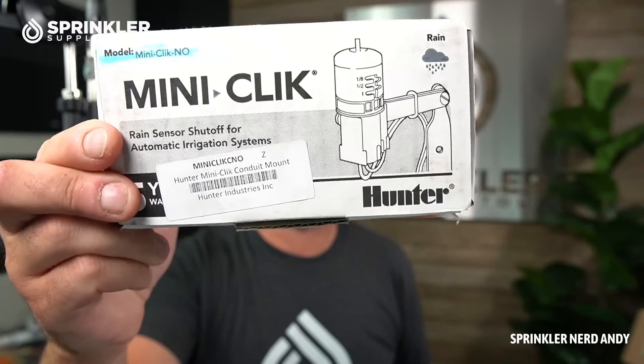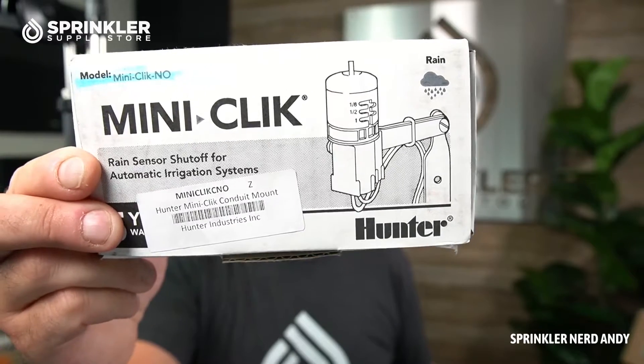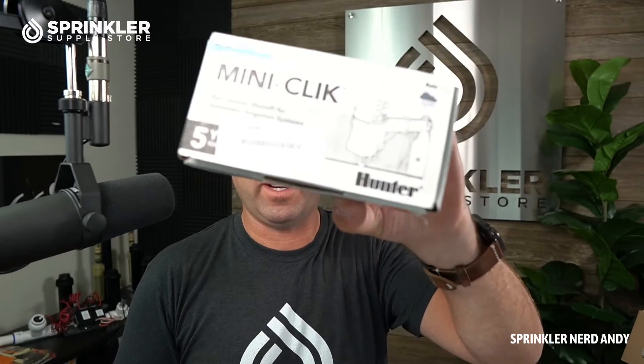Number one, I want to show you the Hunter Mini-Clik rain sensor because it's an old standby — very reliable and inexpensive. But I also want to explain what 'normally open' is, because that is not typical, and if you order this particular rain sensor it's very likely it may not work on your system, because most irrigation controllers are normally closed.